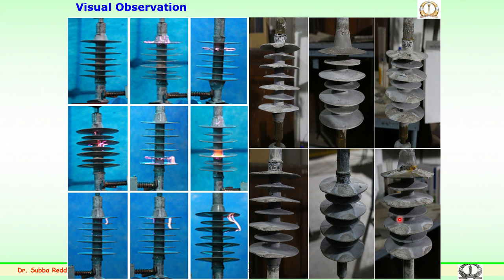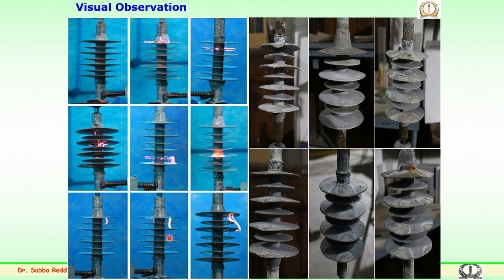Experimental studies have been conducted over a period of time on several types of insulators. Initially the samples are in dry condition; after some period, because of scintillations or discharges — visible near the second shed, the third shed, or between sheds — surface degradation begins. This discharge activity is completely random in nature and depends on the salt, the conductivity of the solution, and the dry band and wet band formation during the dripping period when the insulator comes in contact with the high voltage.